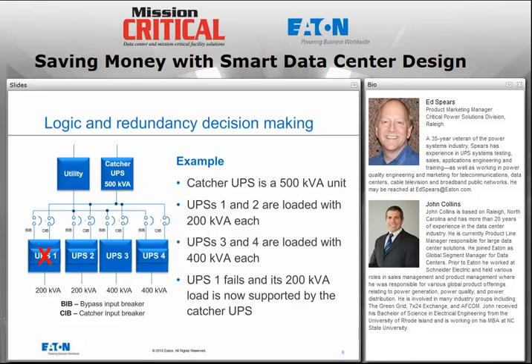And CIB basically stands for catcher input breaker. I also would connect through a different breaker my utility bypass, and that would be connected, again, to the bypass input of each of the 4 primary UPSs through breakers labeled BIB, or bypass input breaker. And as you can see, in normal mode the BIB, the utility fed breakers, are all open, and those breakers that are being fed by the catcher UPS at 500 kVA are all closed. So all 4 of the primary UPSs are being fed bypass power by the catcher.